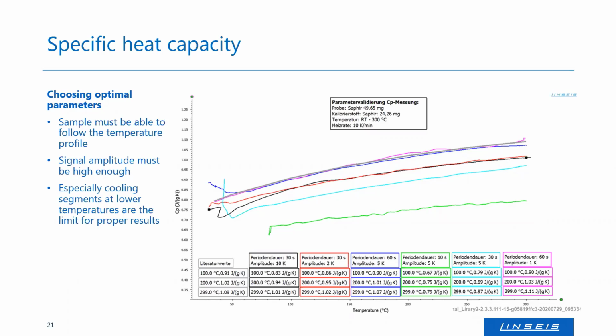But the faster we go, the lower our omega is, so the period, and the worse the result will be. So there are some optimum settings here. Mostly I use a 60 seconds period and an amplitude of roughly 1 Kelvin, sometimes 0.5, sometimes 2 Kelvin or something like this. But this will lead to the best results for this heating rate and this sample. Of course, it is also important to check what my heating rate is. If you, for example, heat with 5 Kelvin per minute, it would be possible to choose a lower period and maybe a higher amplitude or something like this. This depends on your needs and of course also on your sample.